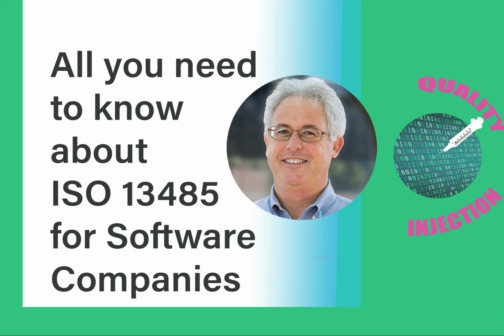I used to have to support device failures as an R&D engineer. We would have lead failures. We'd have electronic failures. There's something called fibrosis that would build up, and that would create so much impedance around our lead, we couldn't deliver electrical current. I wouldn't know about that for 6 months because our patients wouldn't go and see their doctor but once in 6 months. If that happens, the device stops providing therapy and the disease state returns.